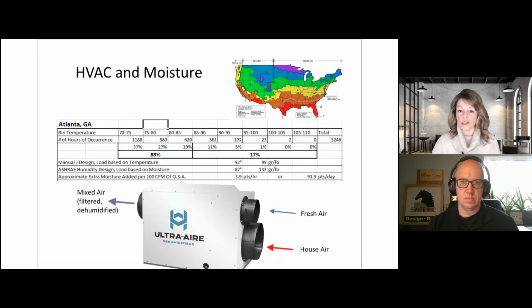As a homeowner, you can't go out and just switch your 50 CFM bath fan to an 80 CFM bath fan and think you can run it all the time without creating other problems. So, no good deed goes unpunished, unfortunately. So we've got to think about the consequences.